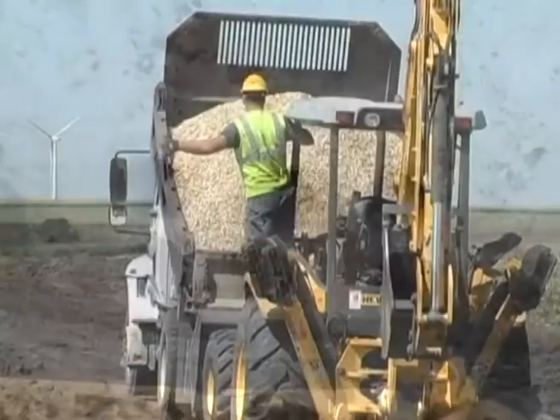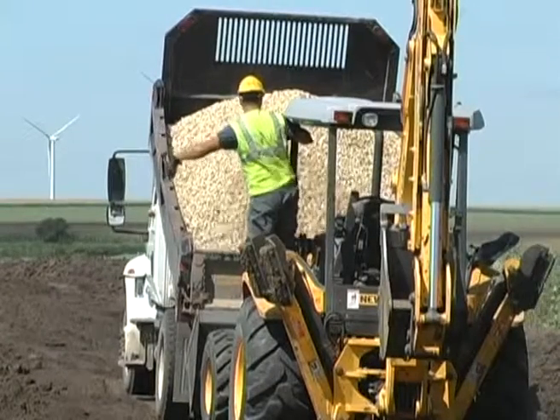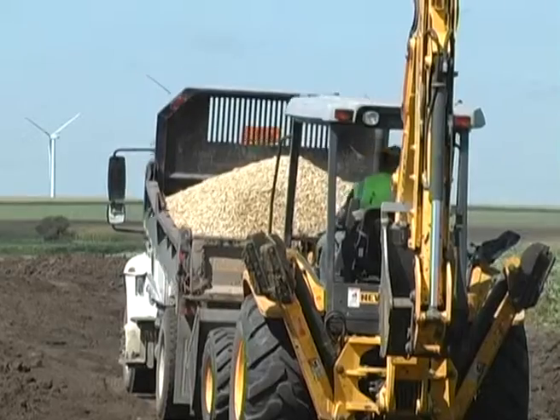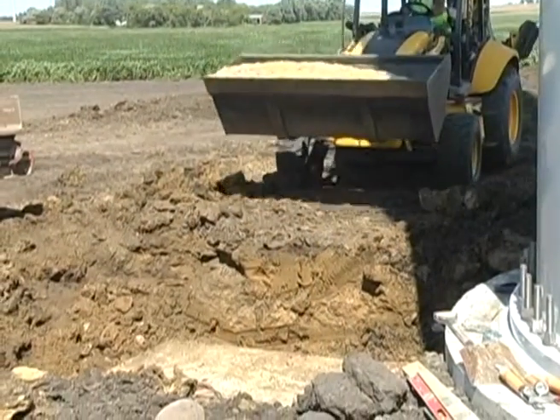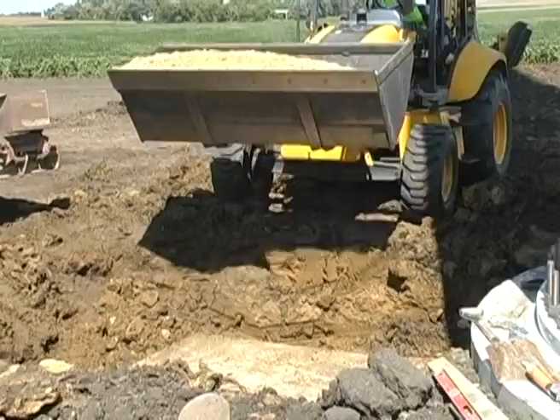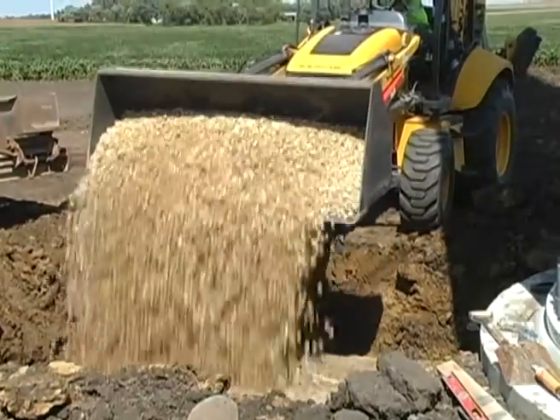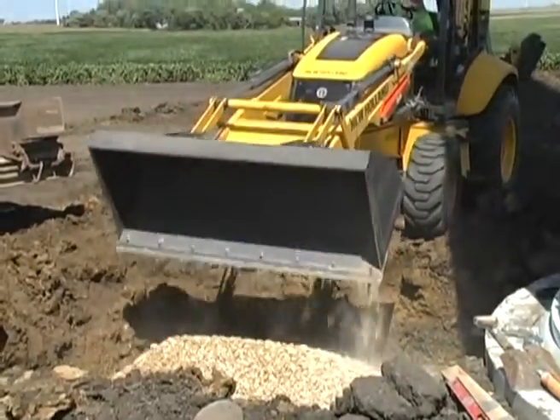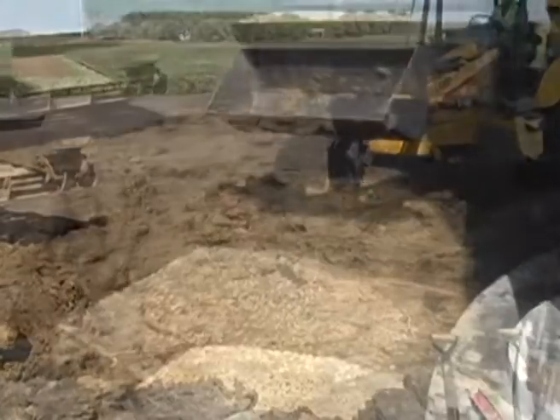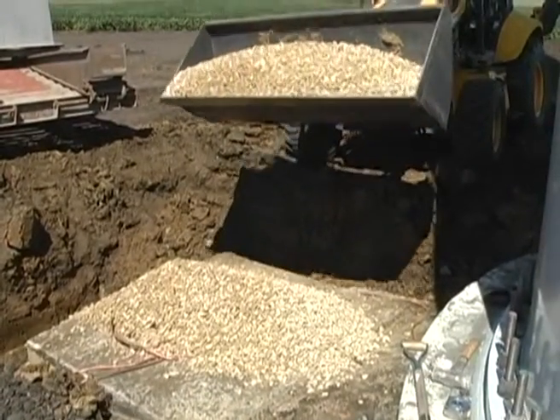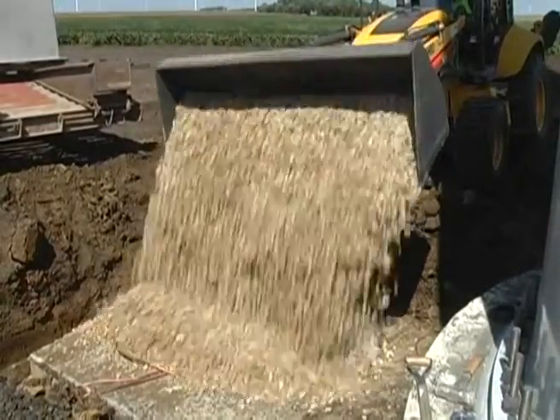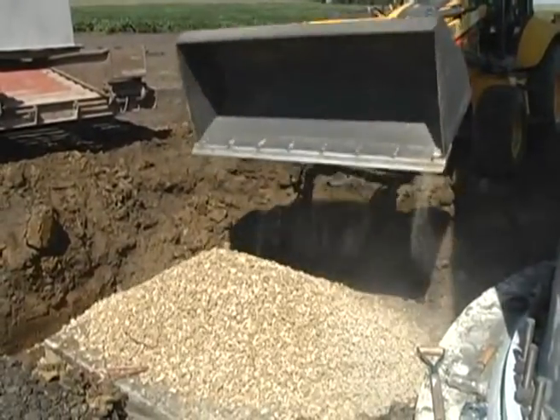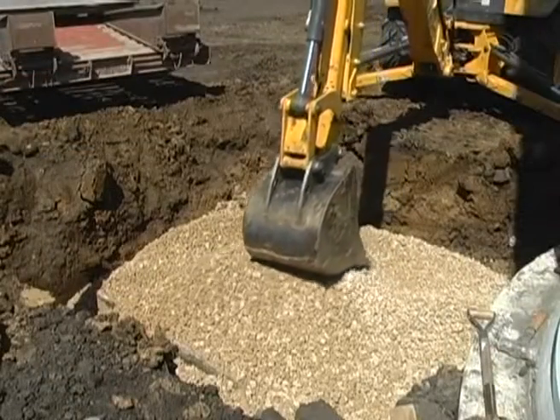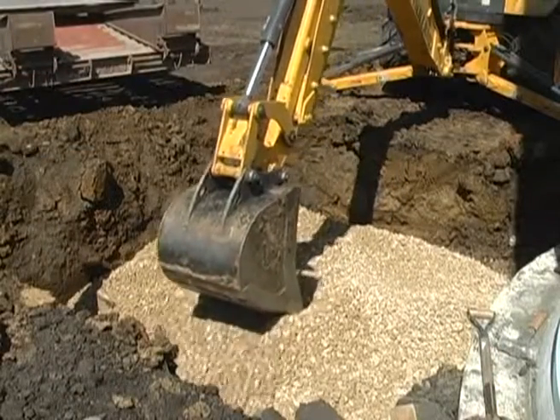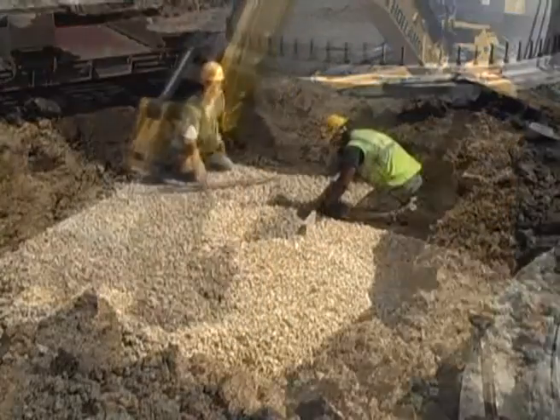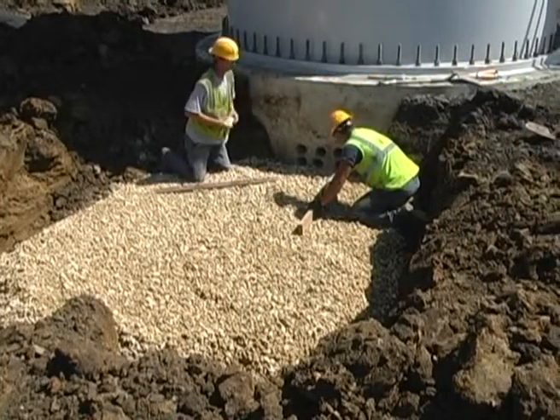A crushed stone base is prepared. The stone should be between 3/4 and 1.5 inches. The depth of the stone base should be several inches to allow the box pad to be leveled and to match up with the pole base top. Care should be taken to level the stone under the entire area of the box pad to prevent pressure points on the flanges.